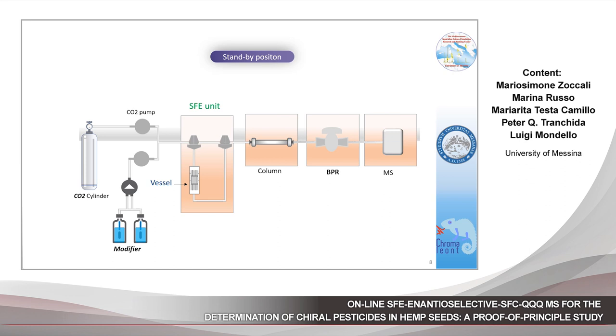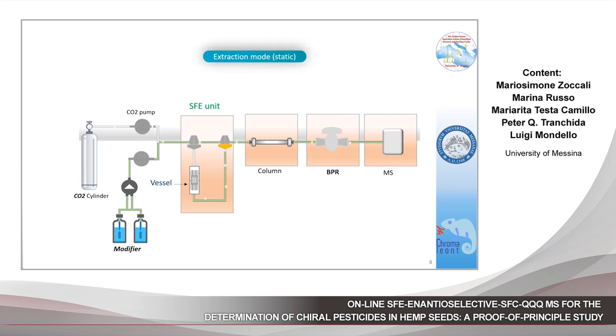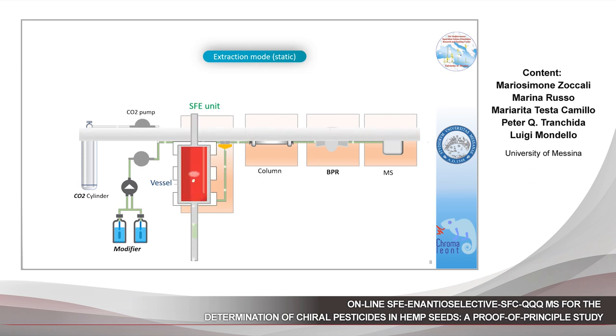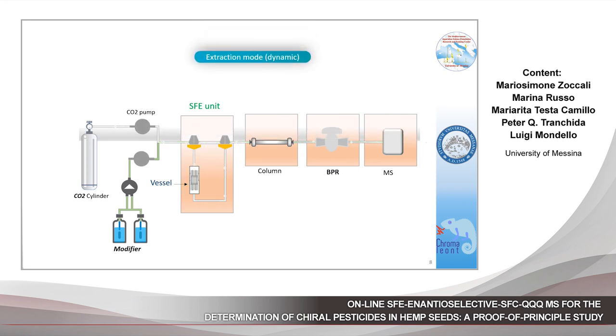The animation shows how the instrument works. During the standby position, both the CO2 pump and the modifier pump flow through the analytical column, the back pressure regulator, and are finally directed to the MS without any split. During the extraction mode — called static extraction — by switching the first valve, it is possible to divert the flow from the CO2 pump and modifier pump in order to fill the extraction vessel. The extraction vessel can also be heated up to 70°C to improve extraction efficiency. At the end of the static extraction mode, by switching the valve again, it is possible to transfer the extracted analytes from the extraction vessel into the analytical column.